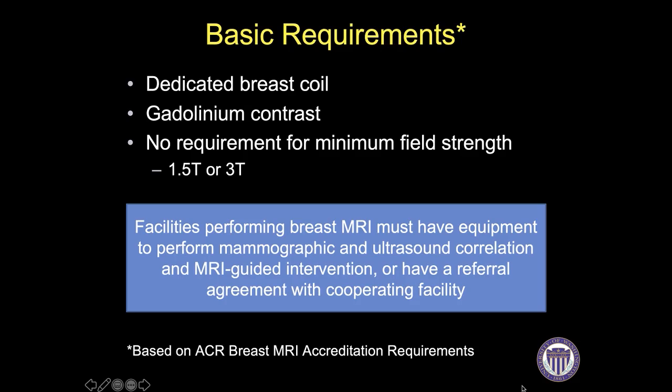Moving on, we are going to talk about basic technical requirements based on the ACR breast MRI accreditation requirements. This includes utilizing a dedicated breast coil and administration of a contrast agent — in this case gadolinium — when looking for breast cancer. Gadolinium is not required to look for silicone implant rupture, and there is no current ACR requirement for a minimum magnet field strength. However, the recommended field strength should be at least 1.5 tesla.